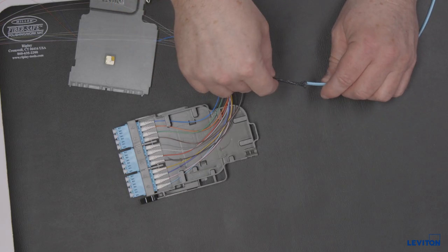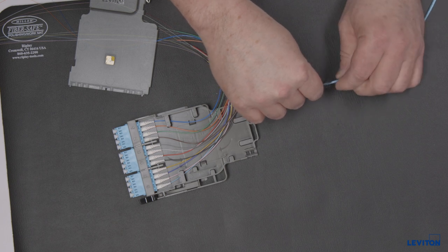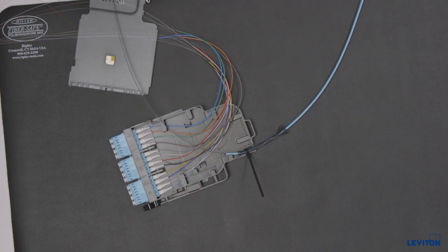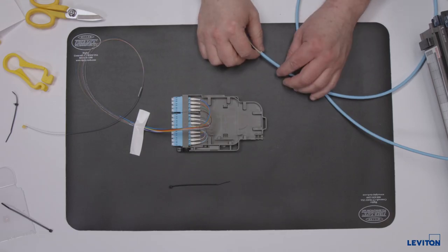When using ribbon fiber in a flat furcation tube, install a short piece of mesh tubing onto the furcated ribbon fiber for securing at the tie-down point. Remove at least 35 inches of outer cable jacket from the entrance point to the splice module.